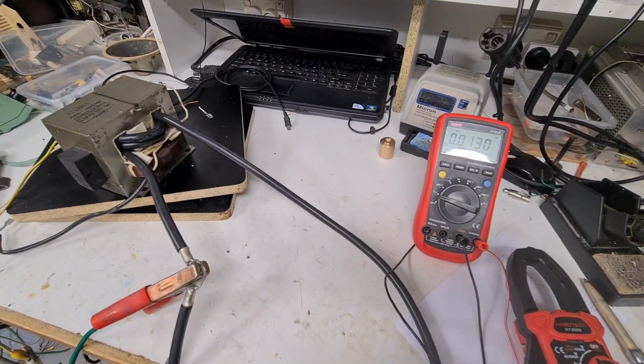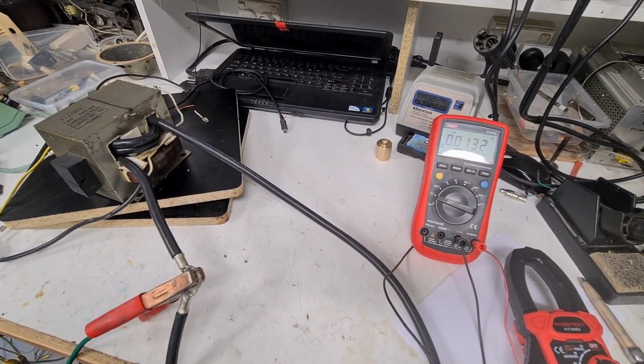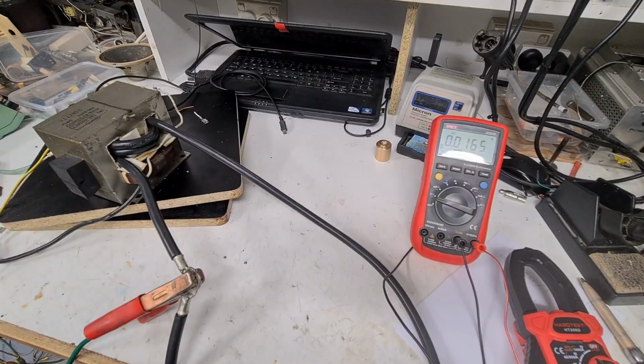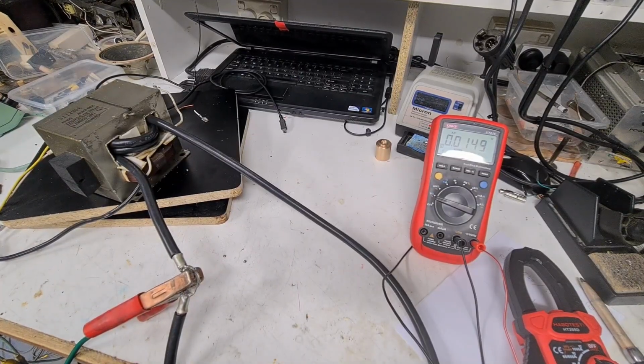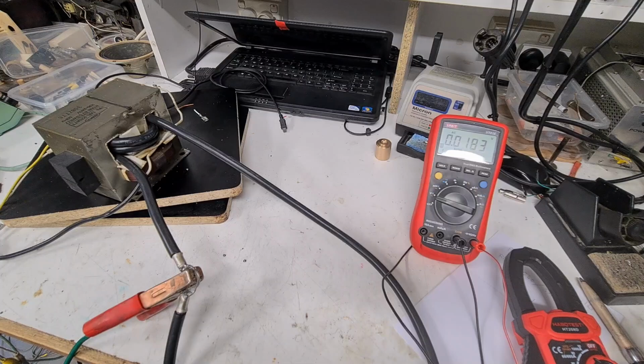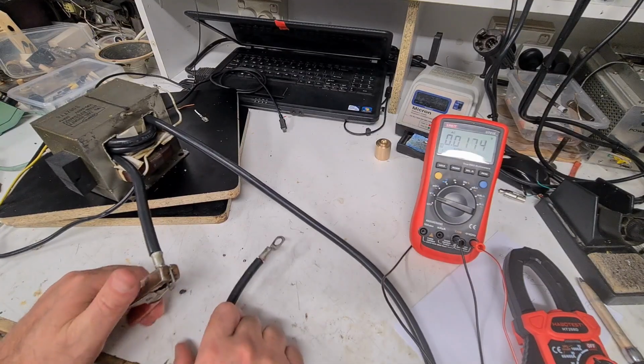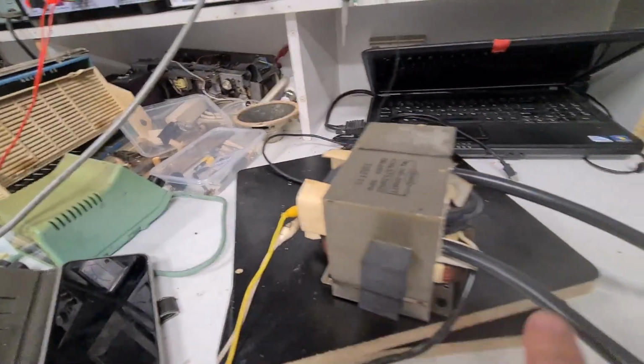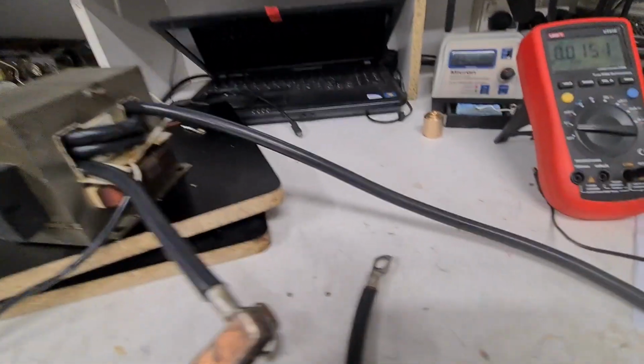I'm going to set the current. Remember, this has an idle current of 2 amps, so technically 2 amps is being drawn, though only at 240 volts. So let me do this test properly. I want to test at 1 amp on the primary and see what the secondary takes. We can use the ratio I got here, 76 to 1.